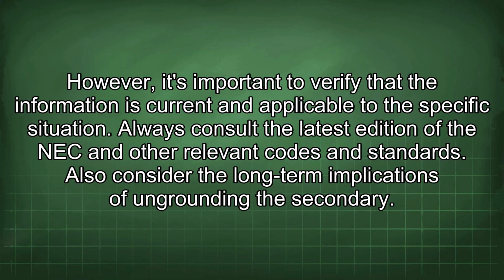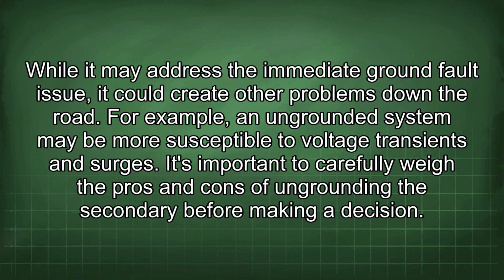Also consider the long-term implications of ungrounding the secondary. While it may address the immediate ground fault issue, it could create other problems down the road. For example, an ungrounded system may be more susceptible to voltage transients and surges. It's important to carefully weigh the pros and cons of ungrounding the secondary before making a decision.